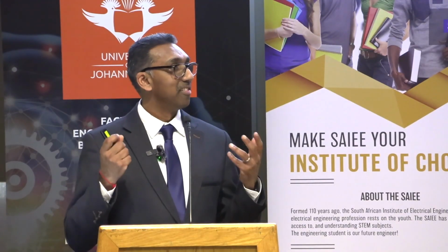Another point on this graph: the light blue is Gourikwa. Gourikwa has 5 units, but its load factor is almost twice that of Ankerlig with 9 units. That's purely because we have a direct pipeline to Petro SA in Mossel Bay, so fuel is not an issue there. However, at Ankerlig we have to truck in fuel using tankers, and I'll go through some of the logistics we have to manage.